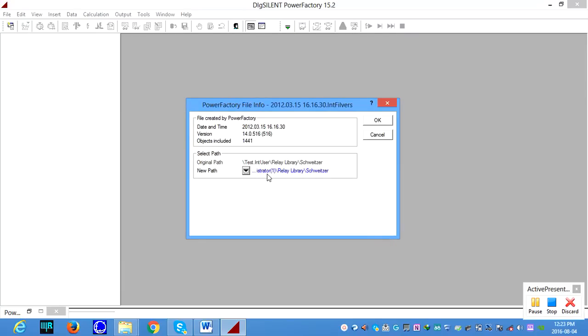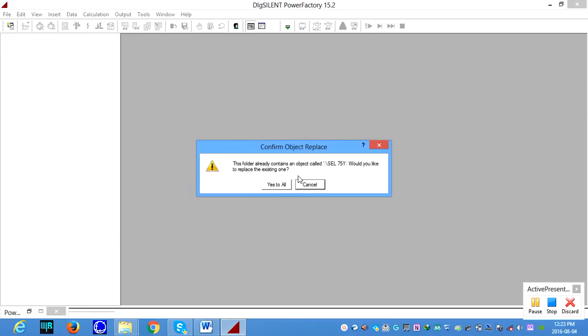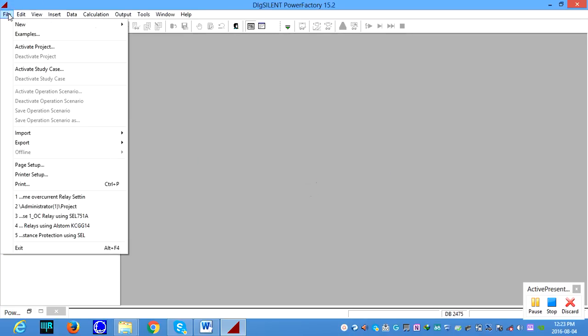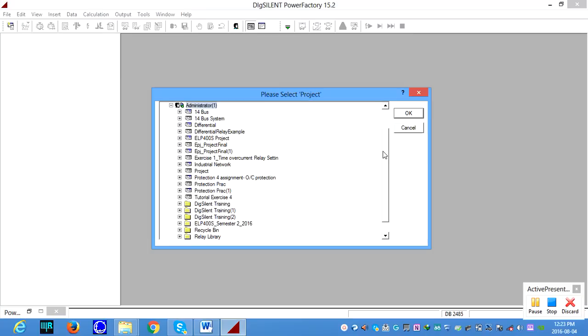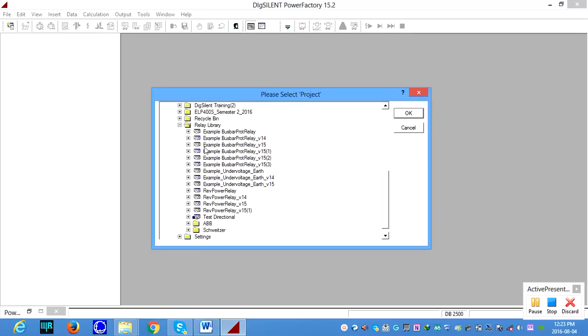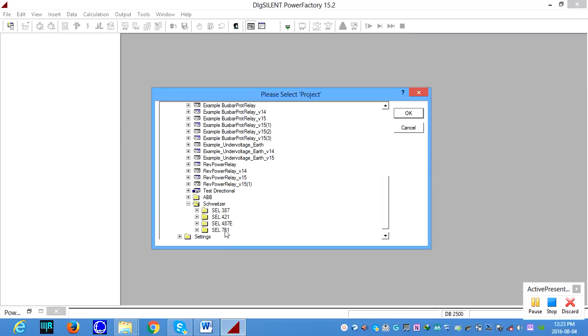If you look here, it goes directly to your database administrator, relay library, and Schweitzer Electric. If you upload, it asks whether you would like to replace the existing one. In my case, I don't need to replace the existing one because I have some settings. In your case, it won't ask you, it just imports. After importing, if you want, you can activate the project and the library comes up. You can see a relay library with different relays available. Under the relay library, you are able to see your SEL, and in the SEL I am using different relays. For this exercise, we are going to use SEL 751, and in the 751, the 751 1 amp relay.